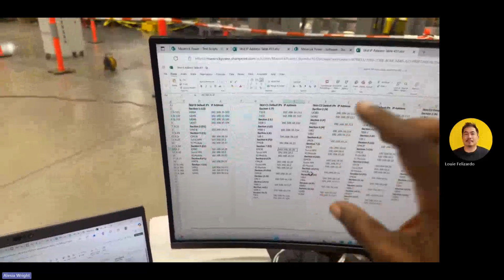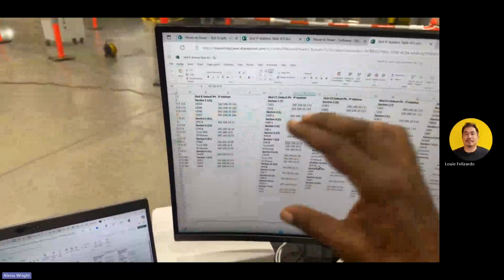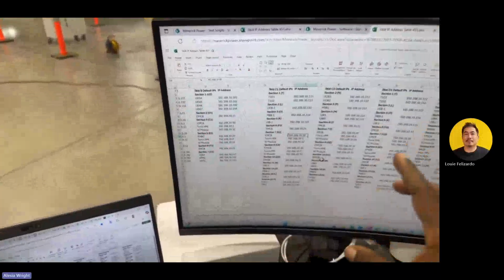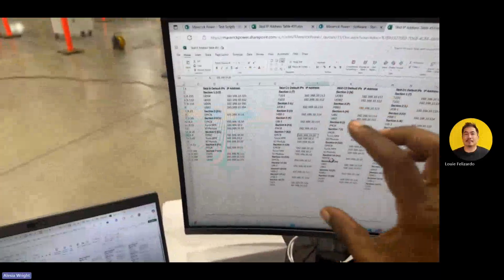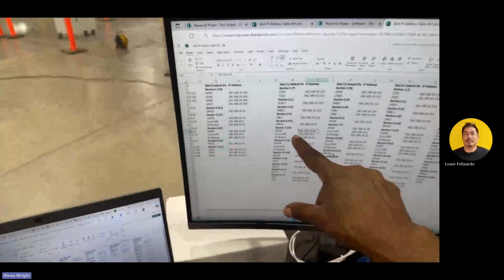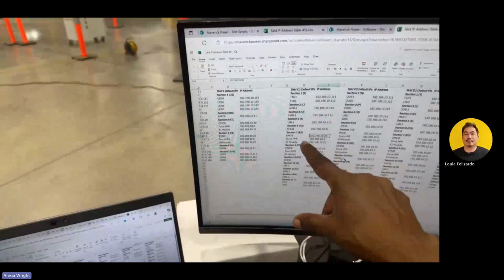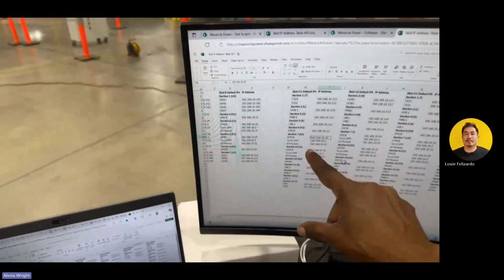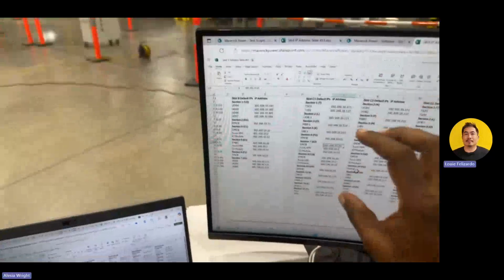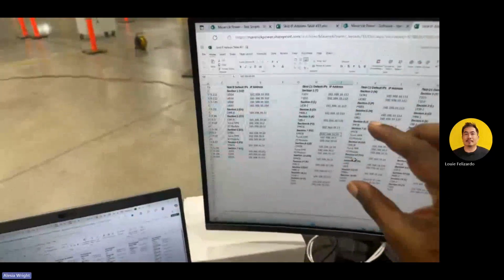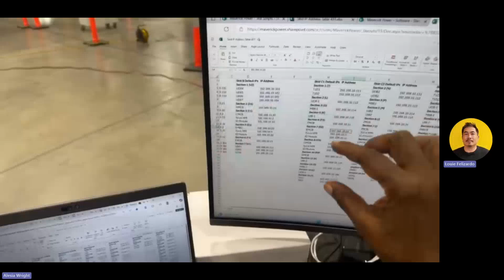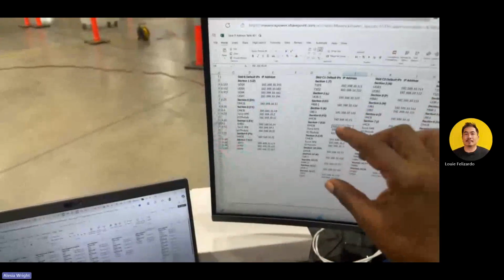Inside of section 7, E2, of course, you have the breaker itself. Also on that unit, E2, section 7, the touch screen is on that unit, which is why the IP address is under section 7. Also, the Wago, which is called the IO module, is actually inside the section 7 unit, which is why the IP address is under section 7.